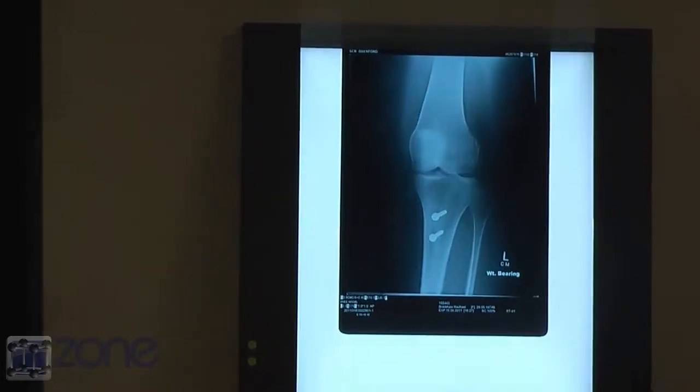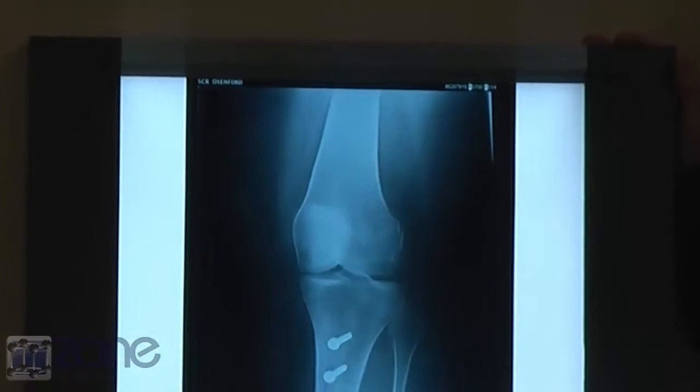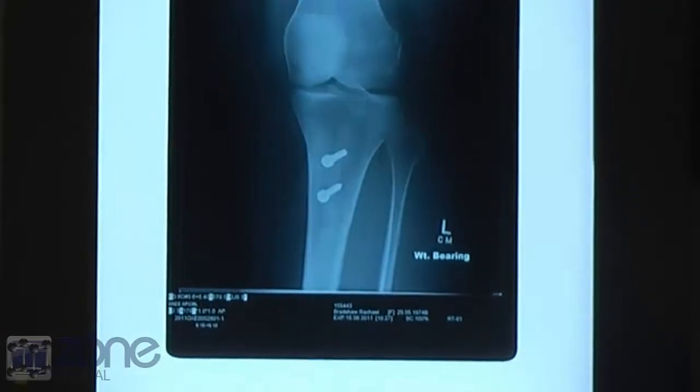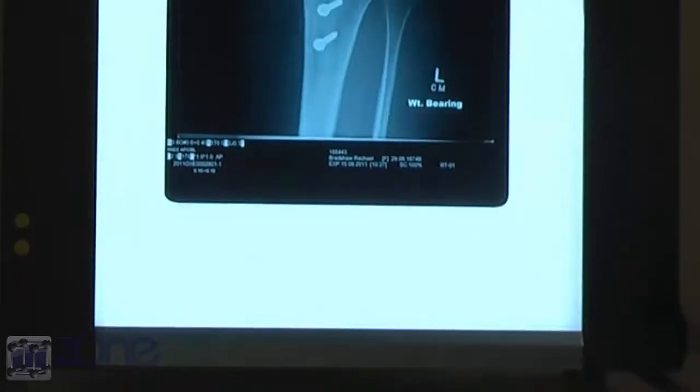Today I will be speaking to you about our single panel LED X-ray viewer made by Minston. A few of the key assets of this device include the illuminator screen that is intense and uniform and can view all types of X-ray films. The alloy aluminium screen is very light, and this compact design and enamel finish ensures durability.